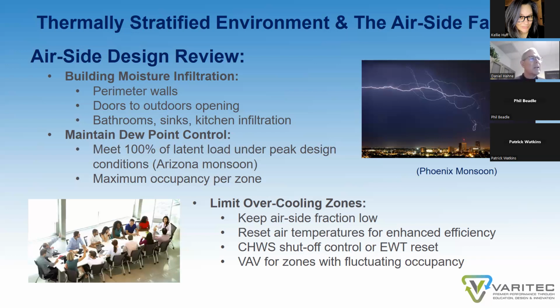And we also need to take into account what the maximum occupancy is per zone. So you do have to be aware that you prevent overcooling in spaces by keeping air fraction rates low. You want to have temperature reset strategies for the appropriate conditions in order to enhance efficiency. You want to look at chill water supply shutoff and entering water reset in the event humidity does become an issue in a space for whatever reason.